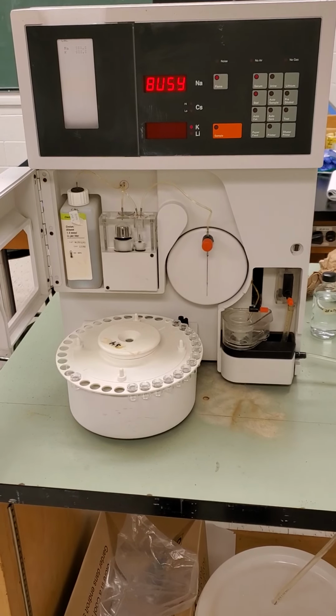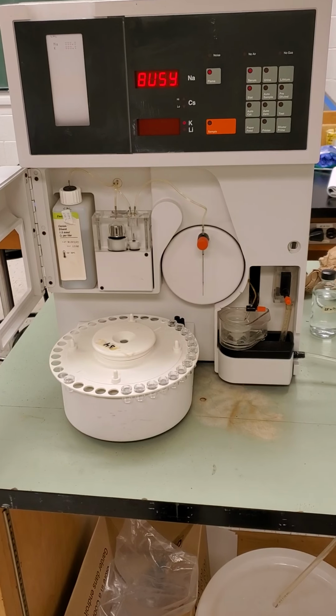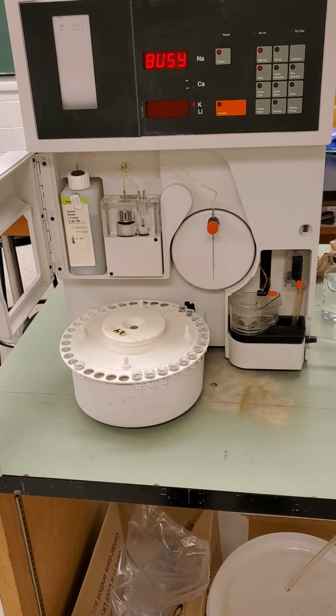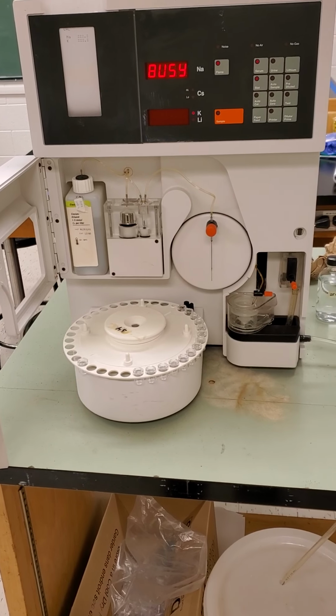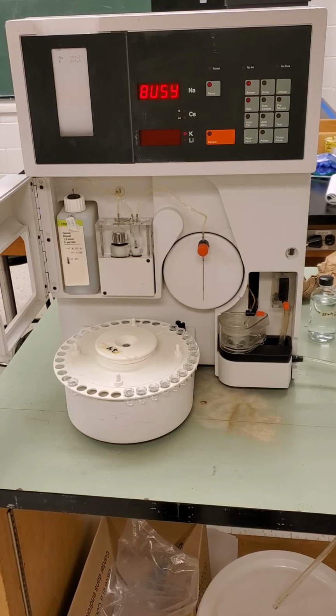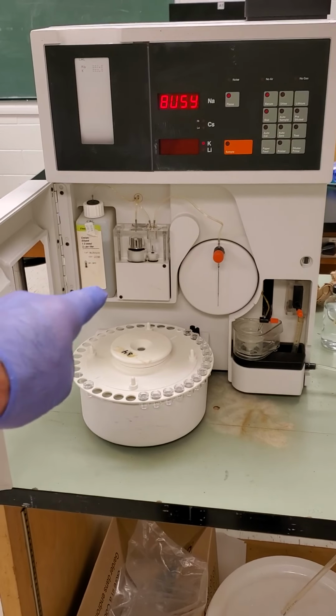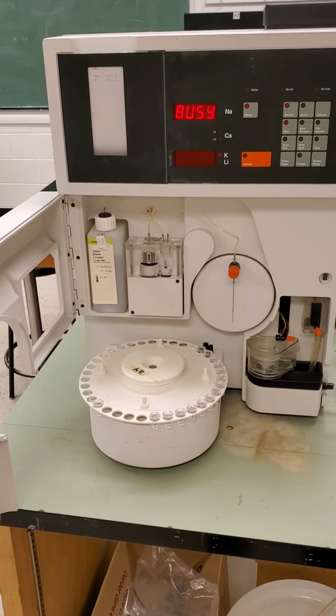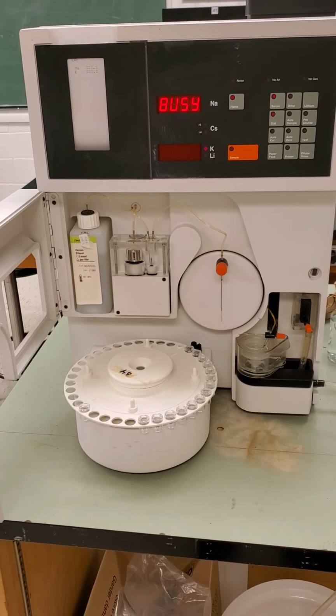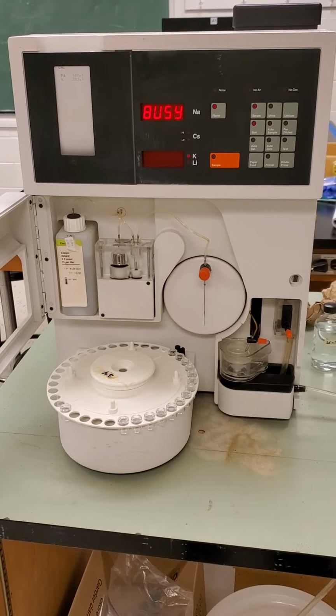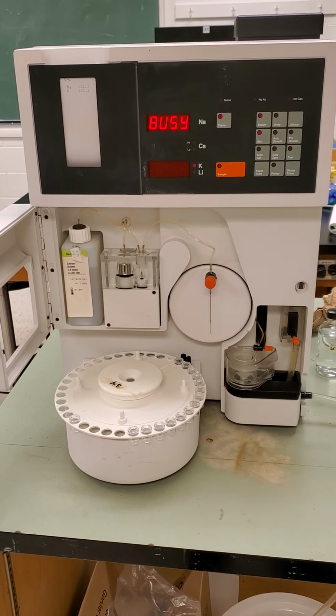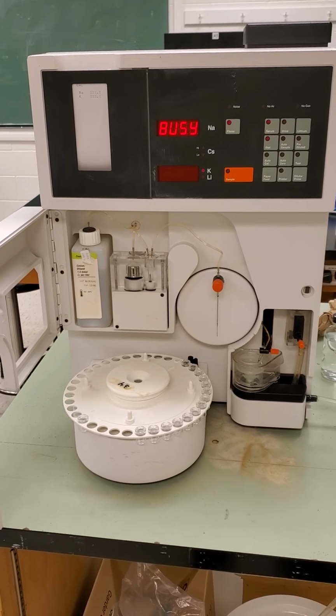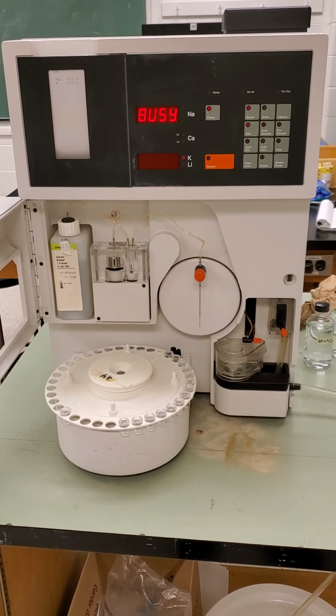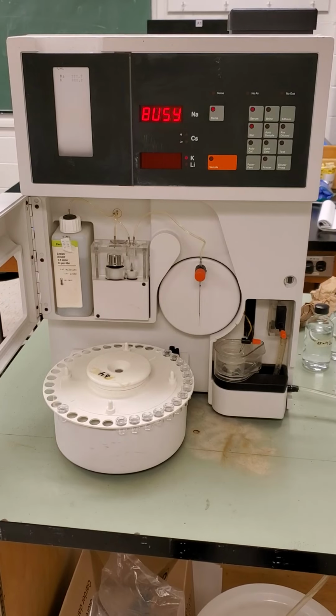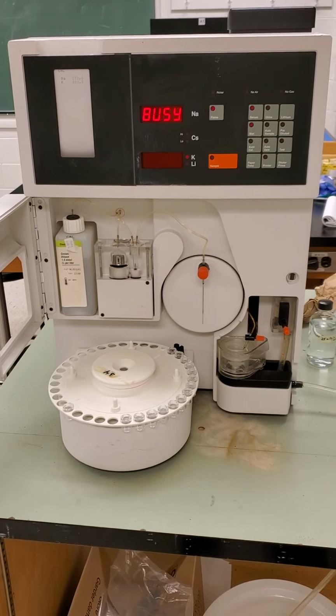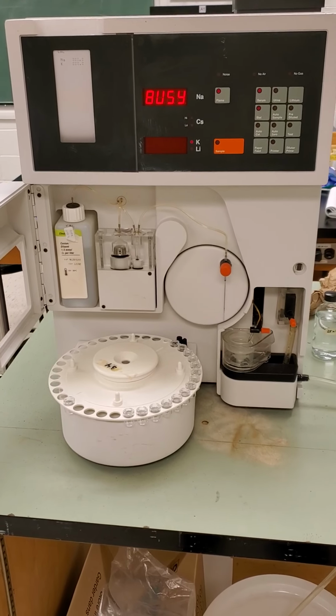It's just filling up the mixing sample chamber there, or sample feeder there, because it's starting to get a little low. Once the busy sign disappears, we can actually start sampling. You just have to make sure that you have enough cesium dilute over there. If you run out during a sample run, it may cause the machine to stop working for a little while. So remember to keep that cesium dilute filled up during operation.